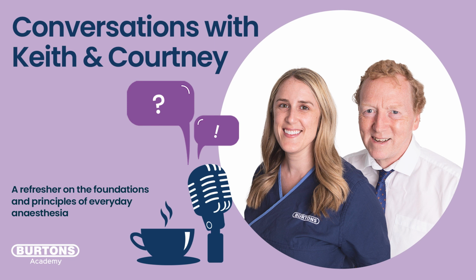But what a lot of people feel tempted to do sometimes is use a side stream sampling line as an art line extension, and that will over-damp their signals, and what you'll get then is much rounding of the signals. And because it gets rounded, you don't reach the peak value, so your systolic value is less. And because it's rounded at the bottom end, you don't reach the diastolic, so your diastolic reading is higher. So you get a reduction in systolic, an increase in diastolic value. The good news for everybody is that the mean arterial pressure is largely unaffected by the degree of damping. So trust your mean. Even if your waveforms are looking a bit iffy, your mean arterial is going to be something you can hang your hat on.